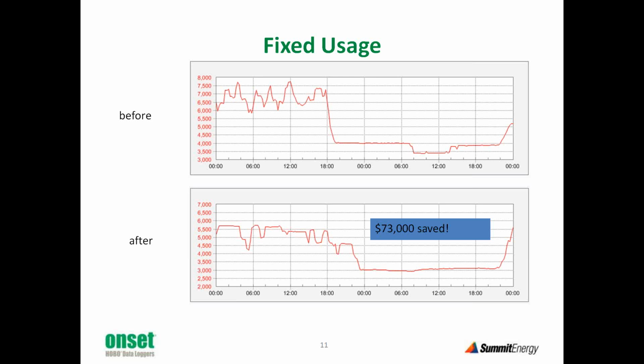So the top graph shows Saturday production load, 7 megawatts. Sunday is an idle day with a load of about 4 megawatts. So they started looking at this load data, scratching their heads and asking, what are we getting for our 4 megawatts on Sunday? They got out their HOBOs and other equipment. They came in on Sunday, just started looking around, asking questions. What's running? Why is it running? And they were able to get the load down to 3 megawatts. So that's 1,000 kilowatts based on their energy rates, $73,000 a year saved, and that's with no capital expenditure.